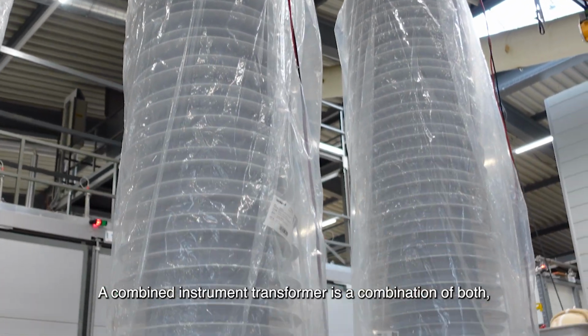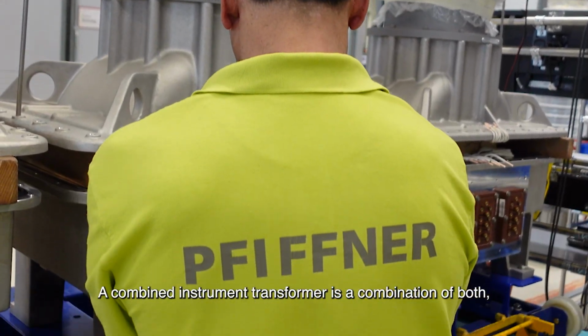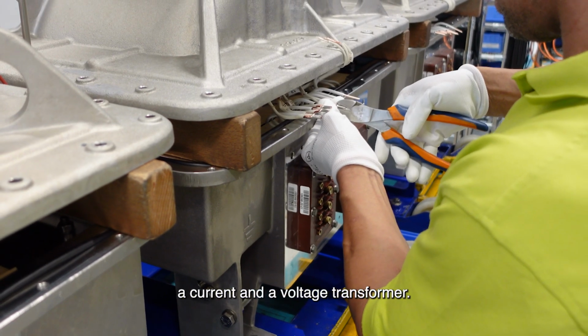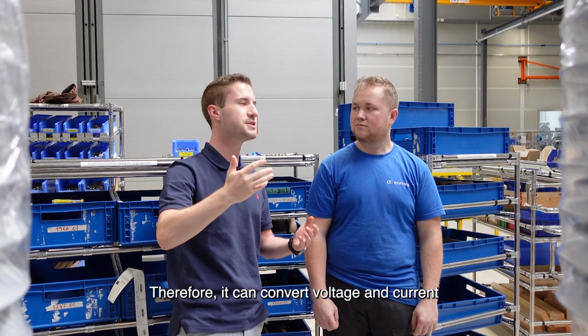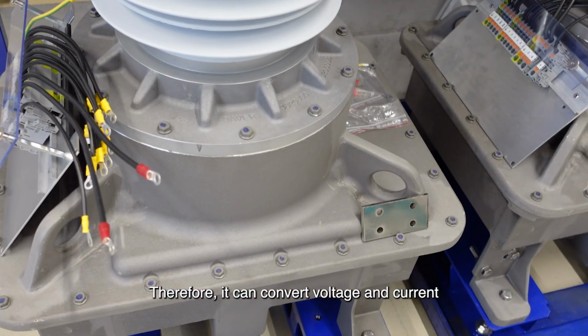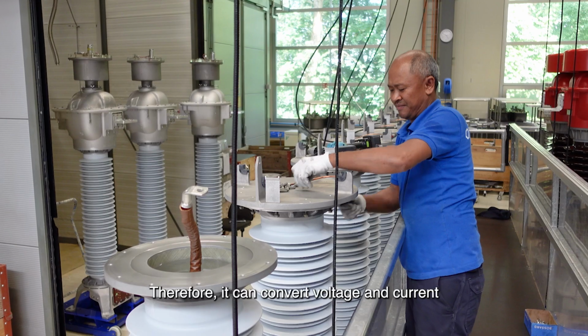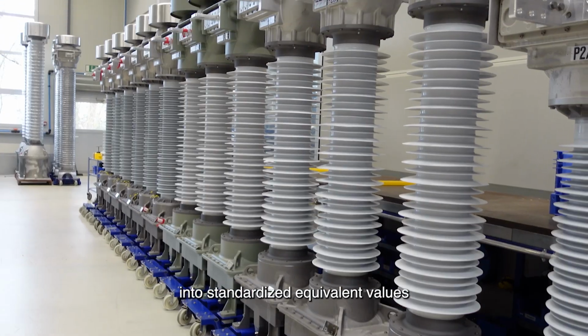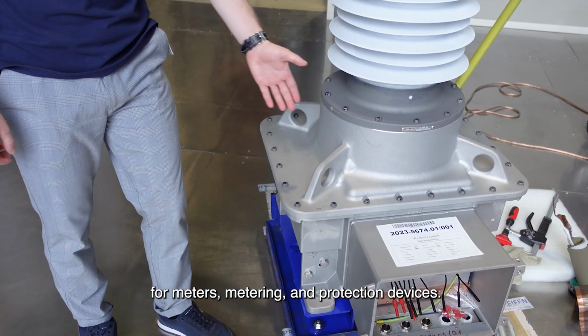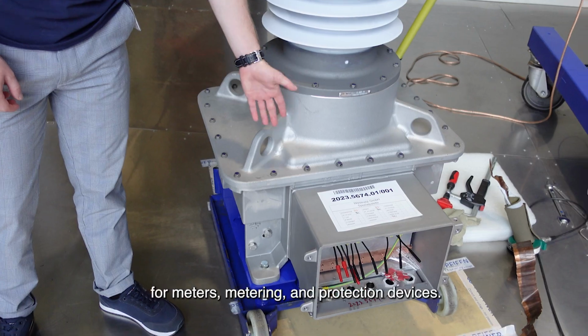A combined instrument transformer is a combination of both a current and a voltage transformer. Therefore it can do both: it can convert voltage and current into standardized equivalent values for meters, metering and protection devices.